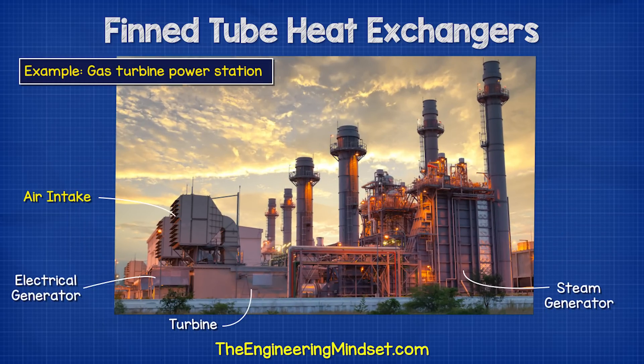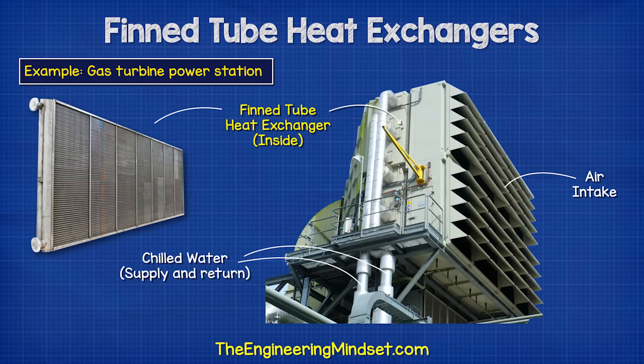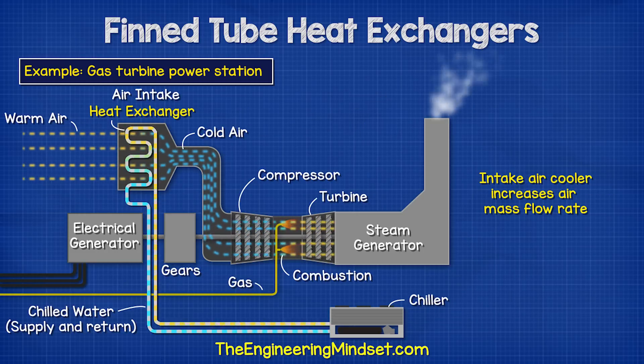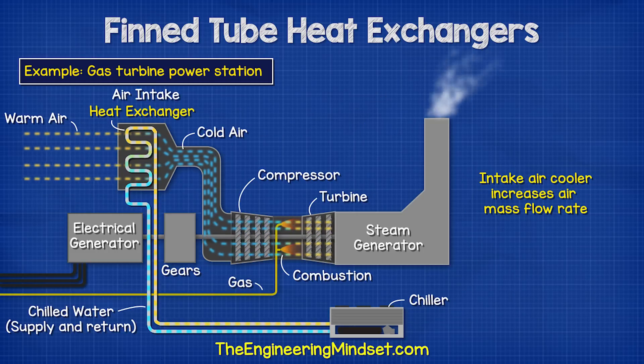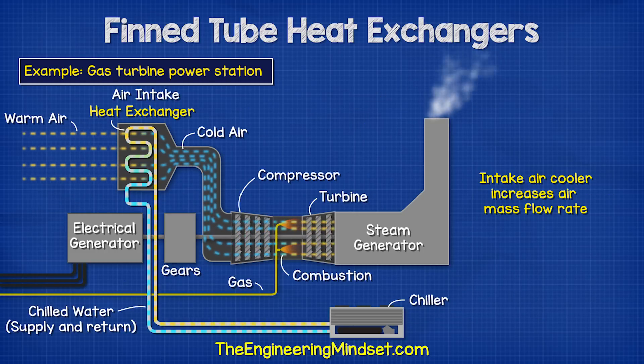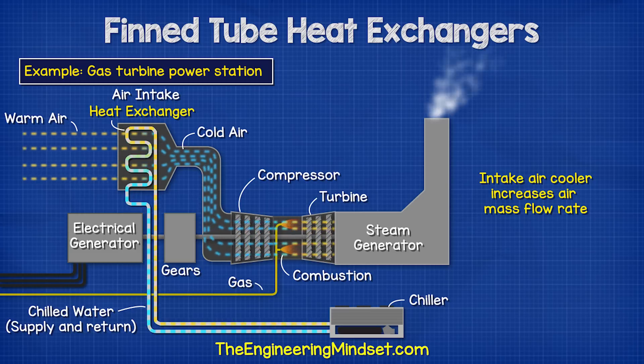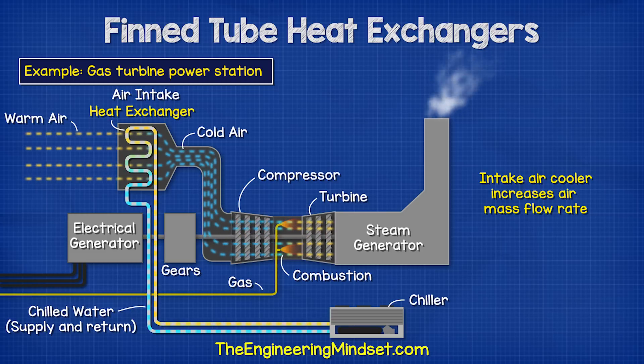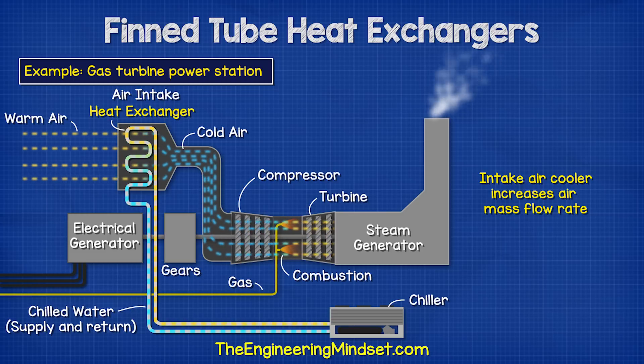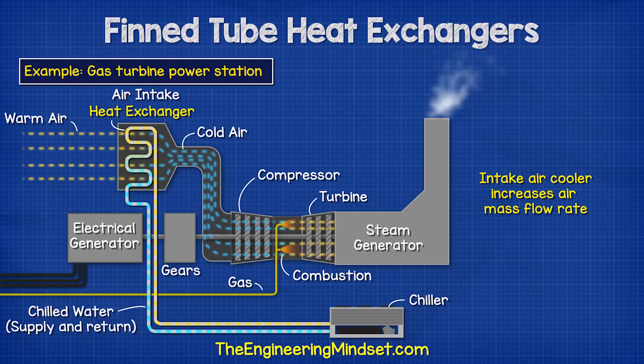For example, these are used on a gas turbine power station to cool the intake air which will be sucked into the turbine and combusted. This helps the turbine run at optimal performance in hot and humid conditions. A chiller pumps cold water to the heat exchanger, which then flows through the tubes.